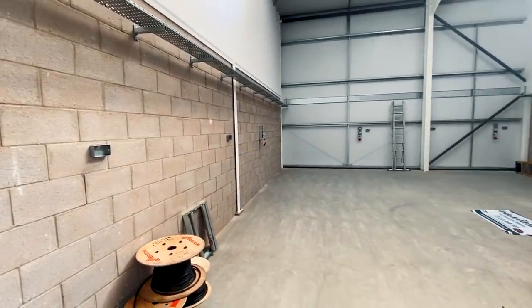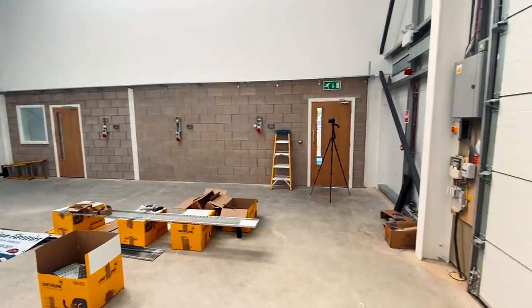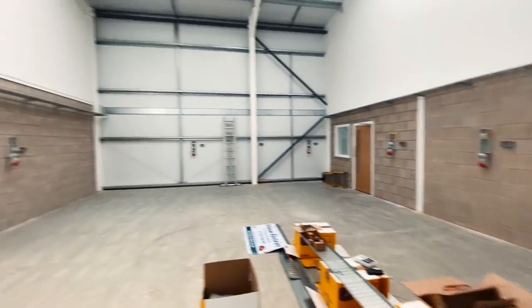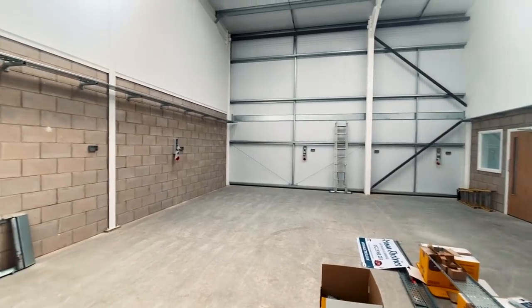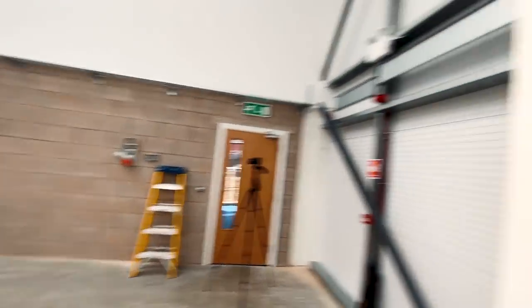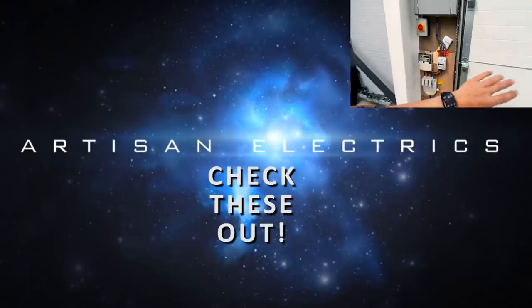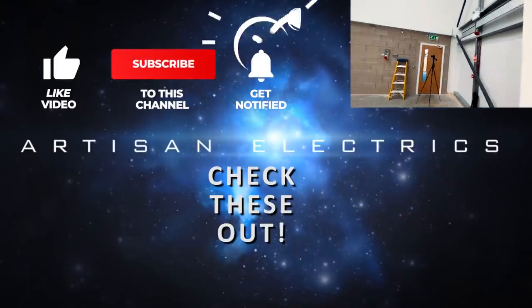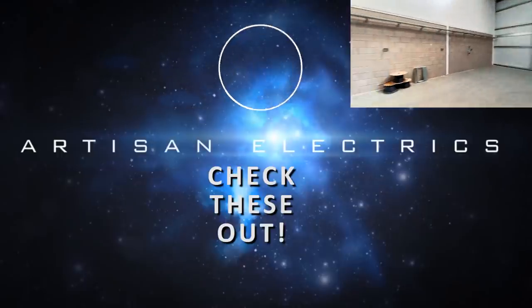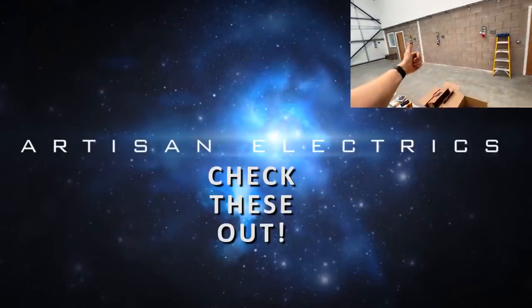So here's a wide angle view so you can see the whole package of what we've done. Pretty pleased - we've had a good day's work, getting all that cable tray in in one day and all the sockets mounted. Tomorrow it's literally just a case of pulling in all the cables, cable tying them onto the cable tray, and then terminating them, connecting all the sockets, and connecting everything into the DB. It's nice because the building's empty so we can literally just cut the main isolator and turn off all the power while we work in the DB - very safe. Stay tuned for tomorrow where I'll show you pulling in cables and connecting up sockets. Thanks for watching and have a great day.